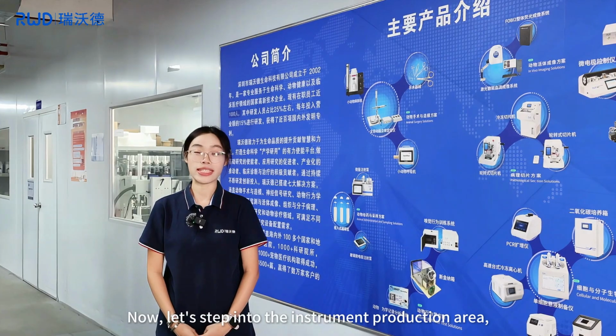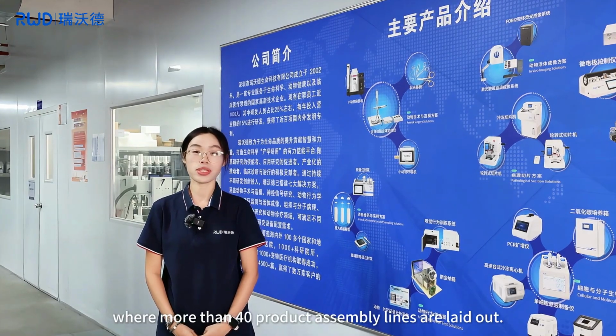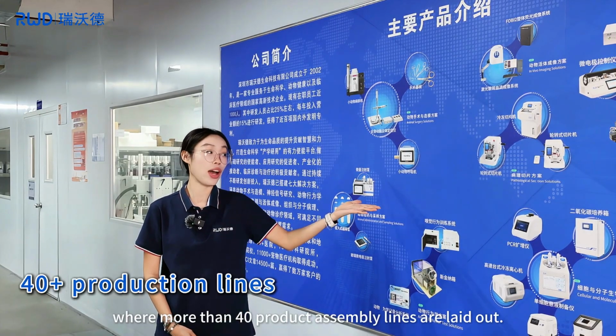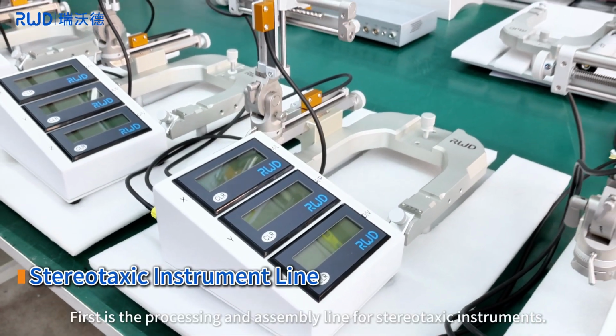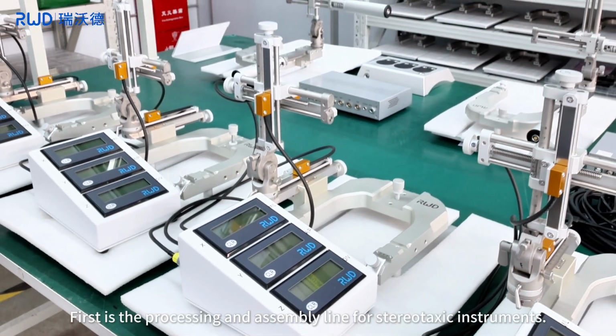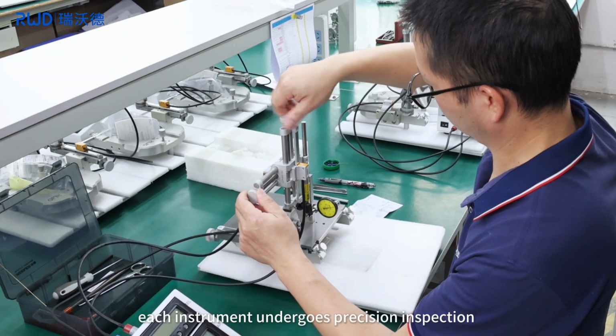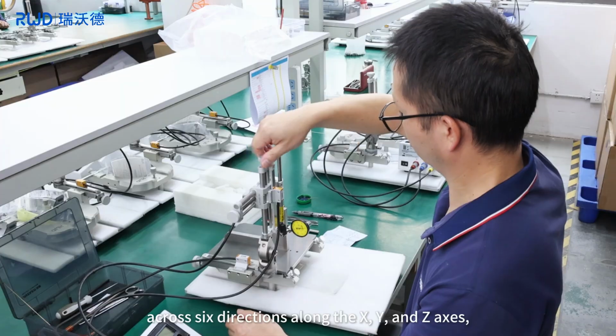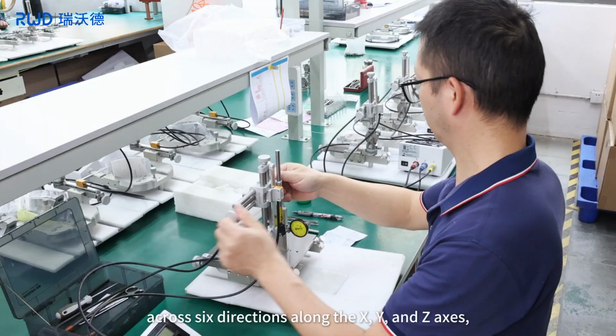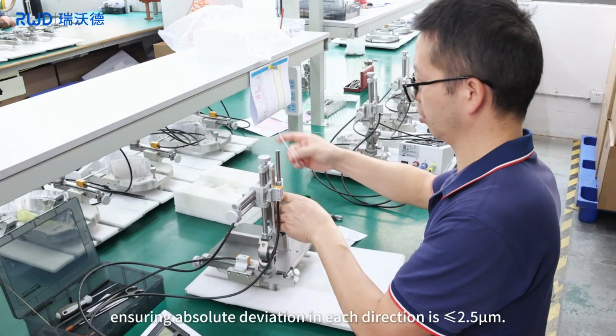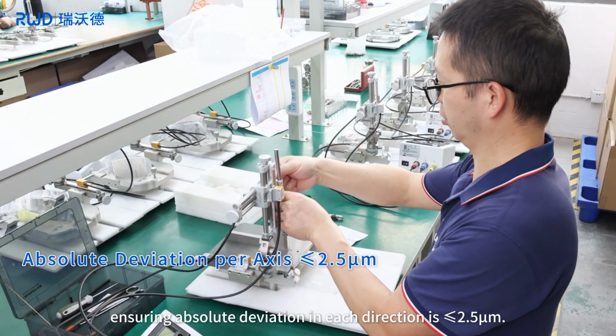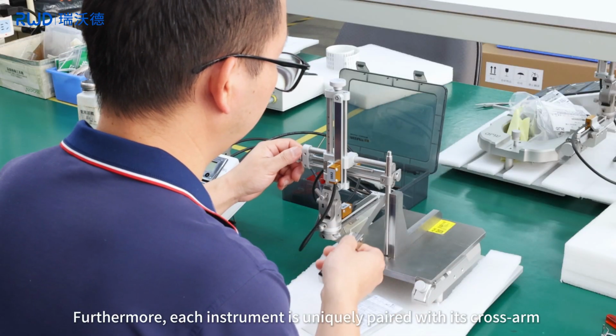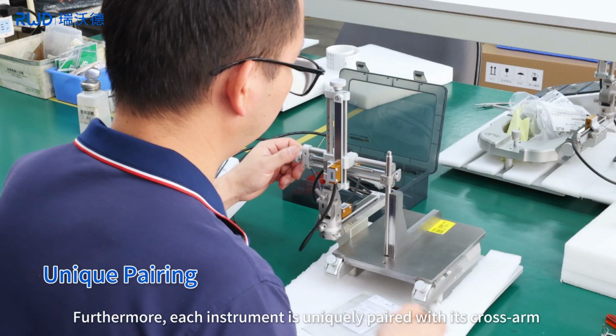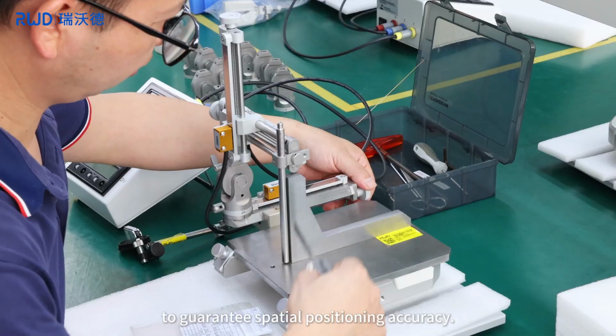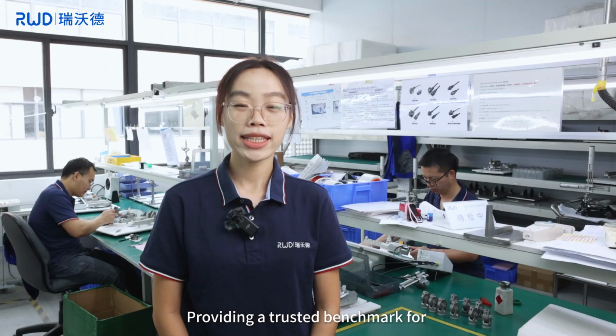Now, let's step into the instrument production area, where more than 40 product assembly lines are laid out. First is the processing and assembly line for stereotaxic instruments. During assembly, each instrument undergoes precision inspection across 6 directions along the X, Y, and Z axis, ensuring absolute deviation in each direction is less than or equal to 2.5 micrometers. Furthermore, each instrument is uniquely paired with its crossarm to guarantee spatial positioning accuracy, providing a trusted benchmark for stereotactic research in laboratory animals.